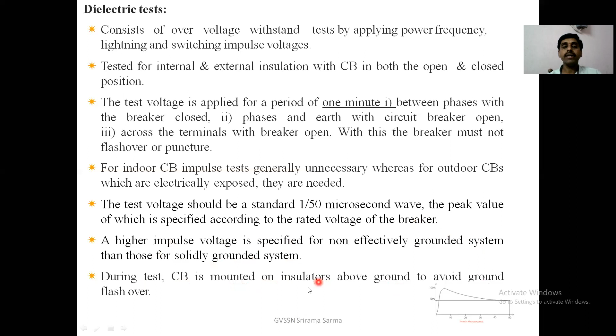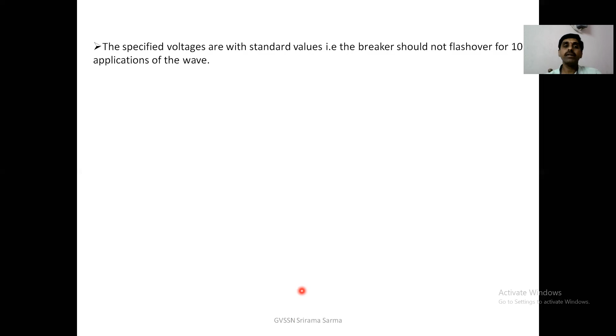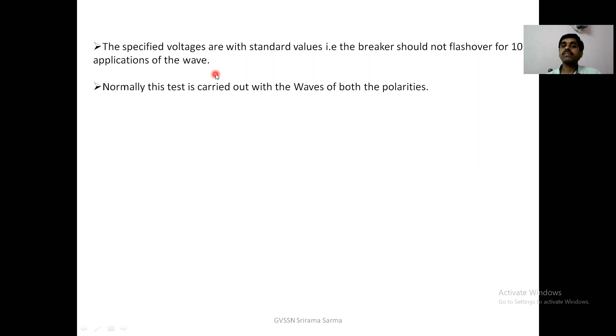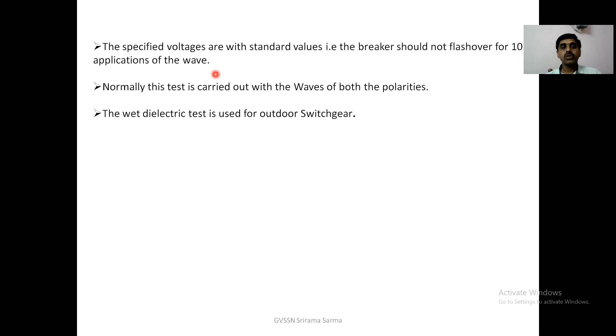Next, we will see the continuation of the dielectric test. The specified voltages are standard values; the breaker should not flash over for 10 applications of a wave. Normally this test is carried out with waves of both polarities. The wet dielectric test is used for outdoor switchgear. In this, the external insulation is sprayed for 2 minutes while the rated service voltage is applied.